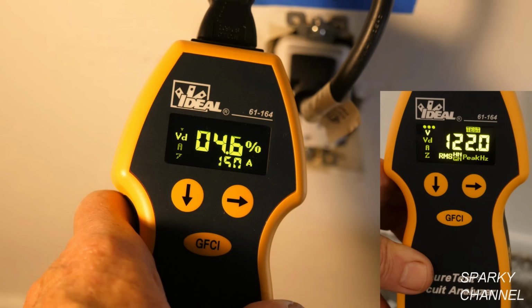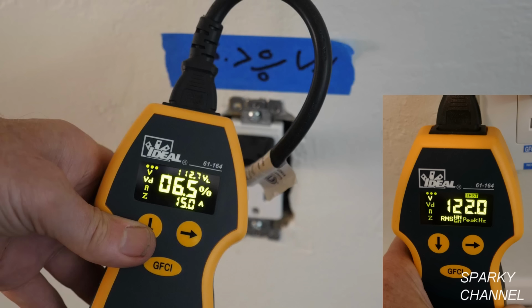The first receptacle, which is the GFCI, reads 4.6% voltage drop at 15 amp load. And that's down from 4.9% before I replaced the receptacle. And the no load voltage is 122 volts AC. We'll be watching the no load voltage to see if that drops at all as we go along. Now the second receptacle now reads 6.5% voltage drop at 15 amp load, down from 6.7% with the no load voltage still at 122 volts AC.